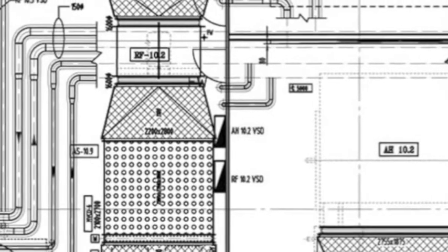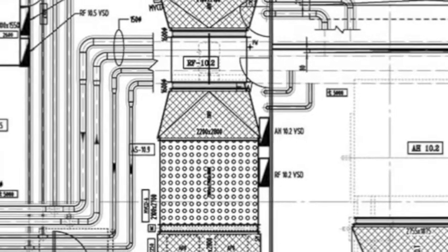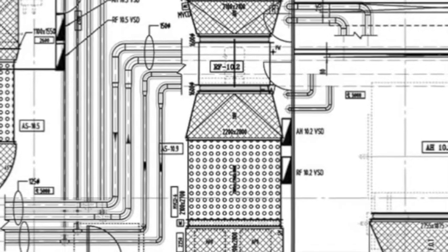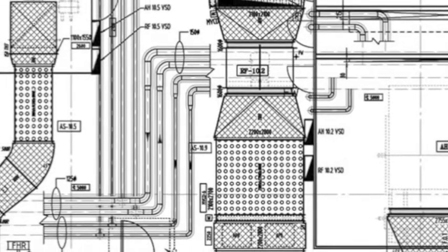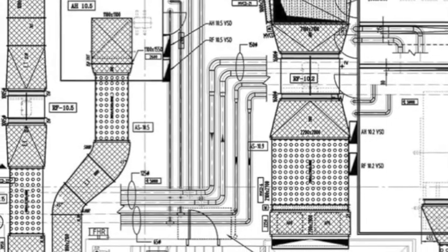Back in 2011, Bob asked me to audit the entire Harrison campus of Boston Medical Center to develop energy conservation measures that would reduce their operating costs, but also improve aging infrastructure. Through auditing the building, we realized that this building had 8 50,000 CFM air handling units with a total air handling capacity of 400,000 CFM for 200,000 square feet.